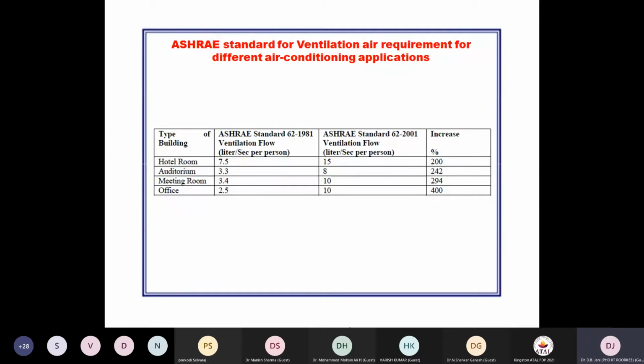Take the example of a hotel room. In 1981, 7.5 liters per second was suggested, but that was ameliorated in 2001 to 15 liters per second. Similarly, for a small cabin, it was 2.5 liters per second, ameliorated to 10 liters per second. So it is a 400% increase in the ventilation airflow requirement per person in terms of liters per second. What are the reasons for that change?